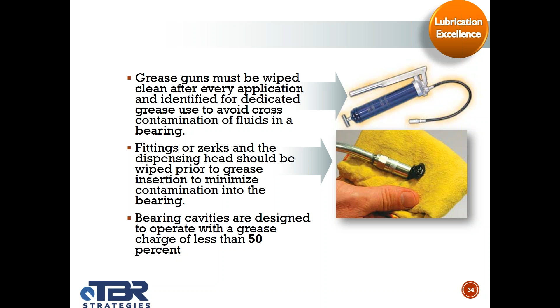And one thing you just got to remember is that bearing cavities are designed to operate with a grease charge of less than 50%. So if we keep packing the grease in there, we're actually displacing that space for cooling, and you can overheat the bearings. And that's why 80% of all bearings never live to their life expectancy.